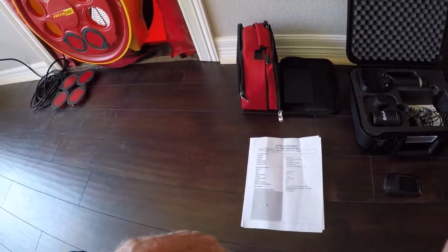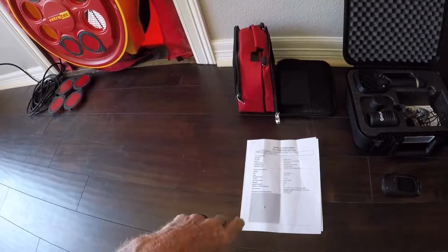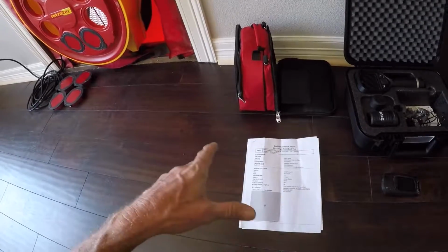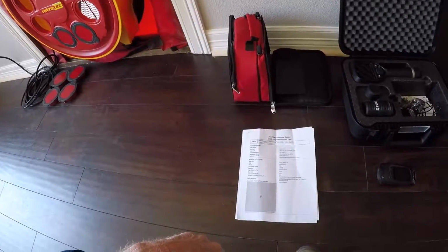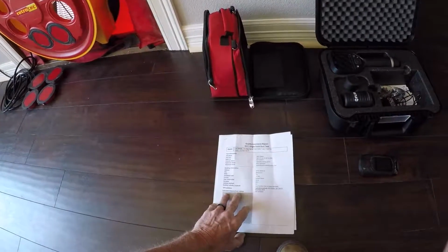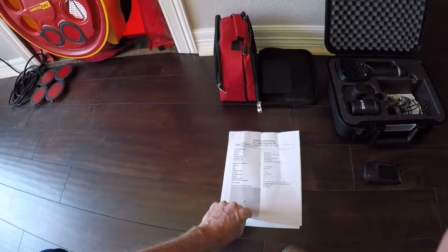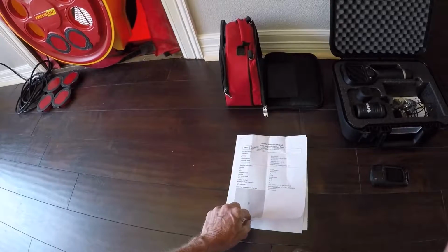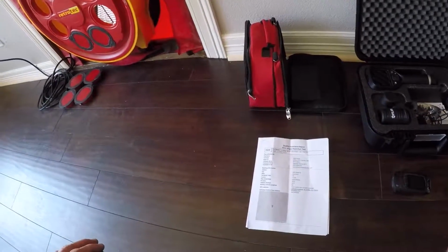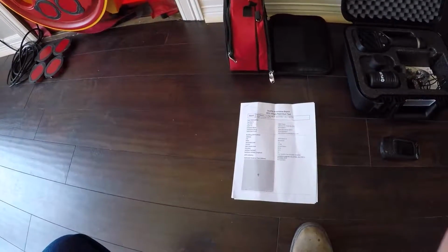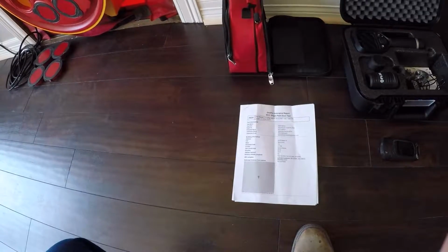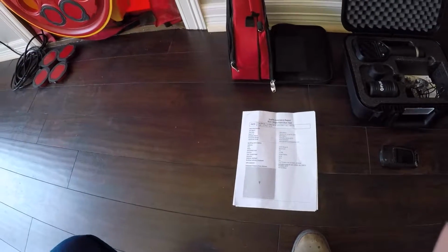I do air conditioning loads and REScheck, IC3s, so many forms, but this is just for reference. I carry it with me. That gives me the cubic feet of the home, square footage for all the tests. As you can see, this particular duct test was 1.9 CFM per 100 square feet, which is excellent.